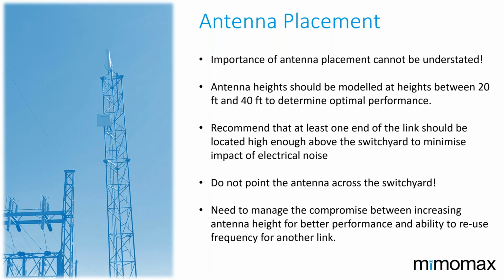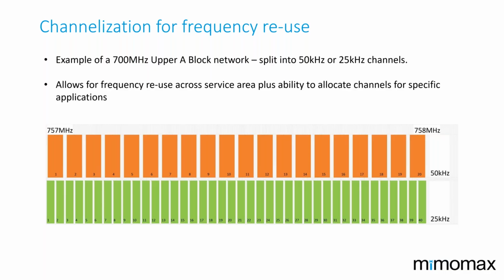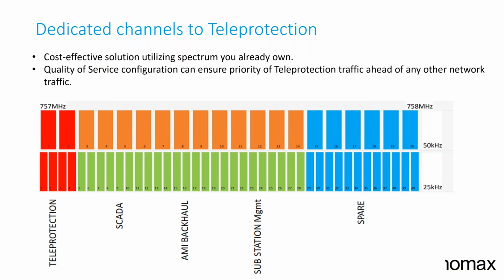Optimizing spectrum. So some of our customers have the luxury, particularly in the US, they've gone and purchased the 700 megahertz upper A block, for an example, and this gives them 1 megahertz chunks of spectrum in the 757 to 758 and 787 to 788 meg bands. And this example really just shows how they're utilizing that spectrum, and they will partition off a number of channels for teleprotection. The rest of the network may be a point to multi-point network supporting SCADA or AMI backhaul or substation automation, and quite often we find I've still got some spare channels to work with. But because we want to make sure that the priority of teleprotection is ahead of others and the QoS is configured as such, we would often encourage our customers to dedicate channels to that.